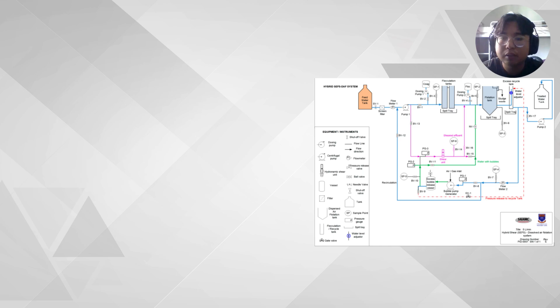So I'm going to present about chapter 4, which is the existing process control system. In this slide, it shows the overall existing process control system of the SEFS-DAF unit. Based on the P&ID, the system operates using manual and semi-automatic control. As you can see, the influent flow, recycle flow, pressure, chemical dosing, and shear intensity are all monitored using basic instruments such as flow meters and pressure gauges. However, adjustments are carried out manually using valve and pump settings. There is no closed-loop PID control, so the system relies heavily on operator experience, which can cause slow response when disturbances occur.